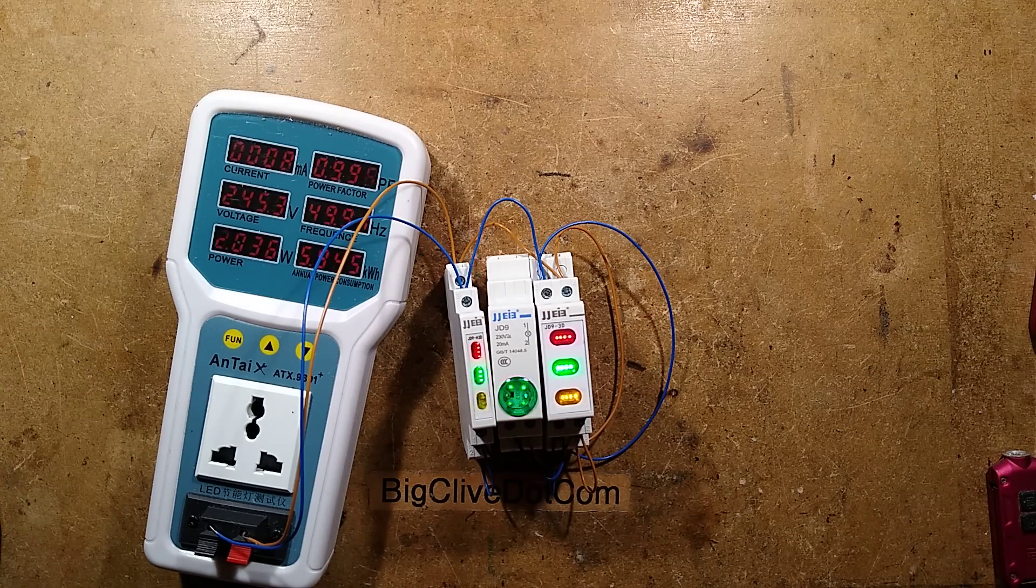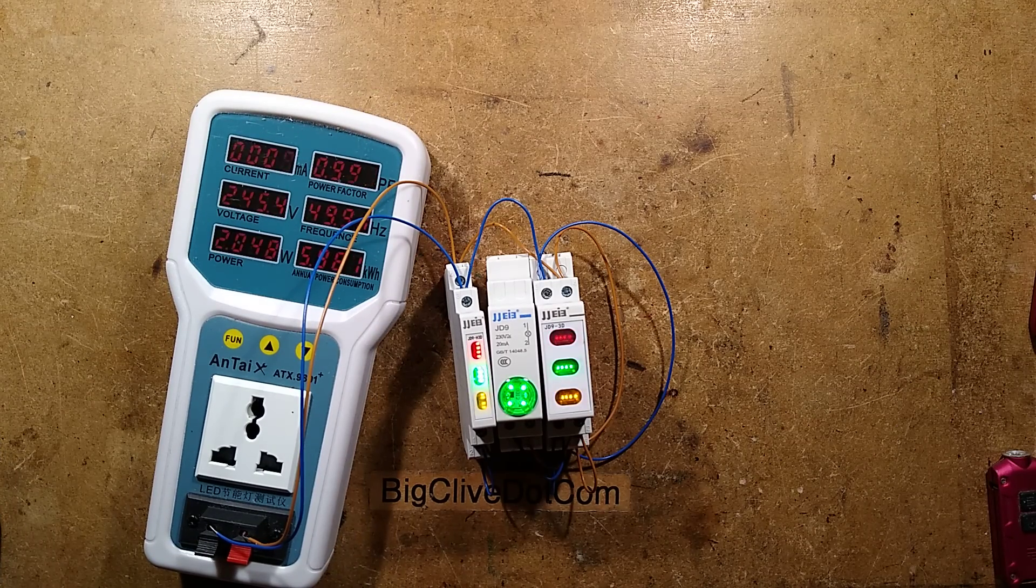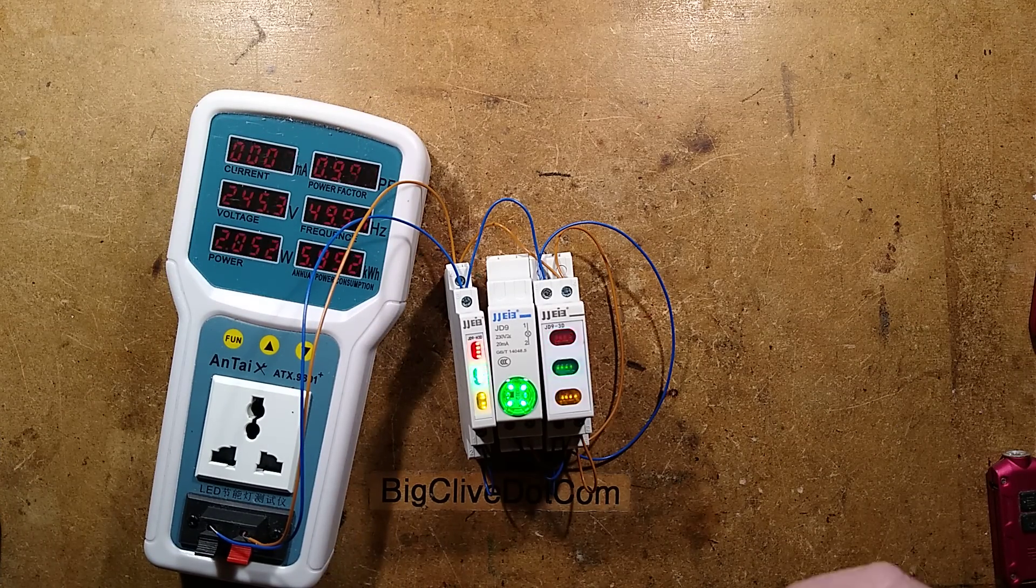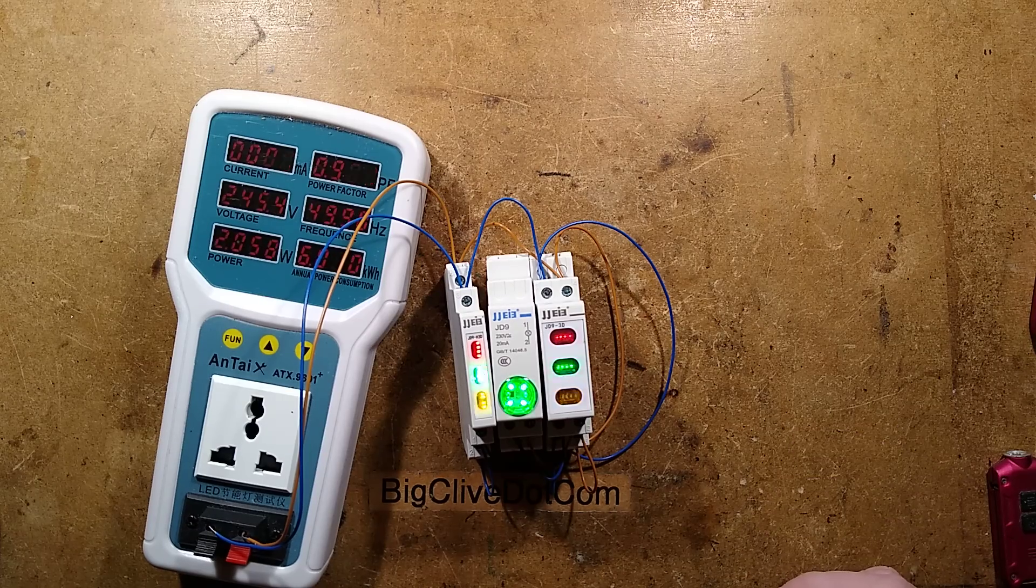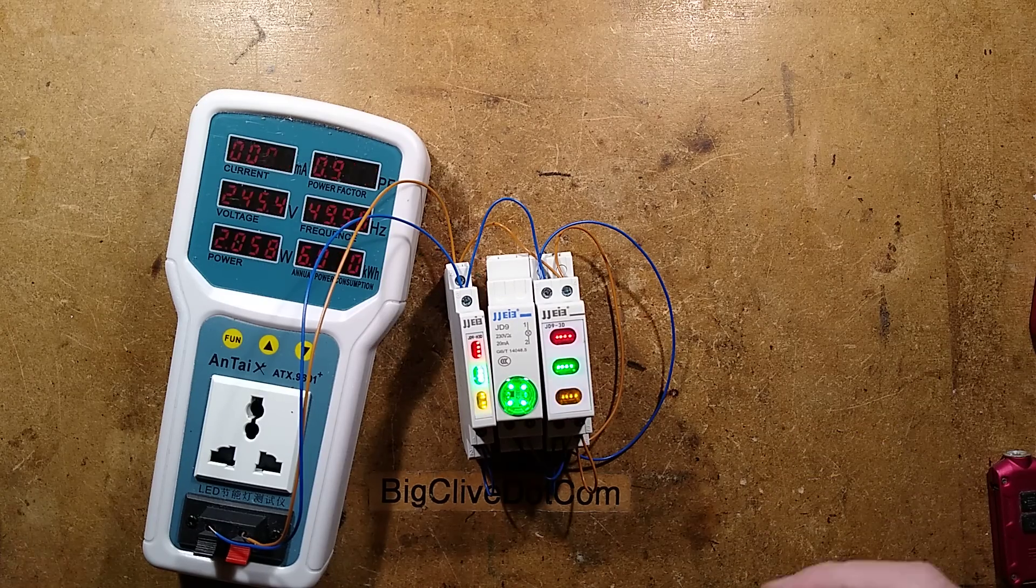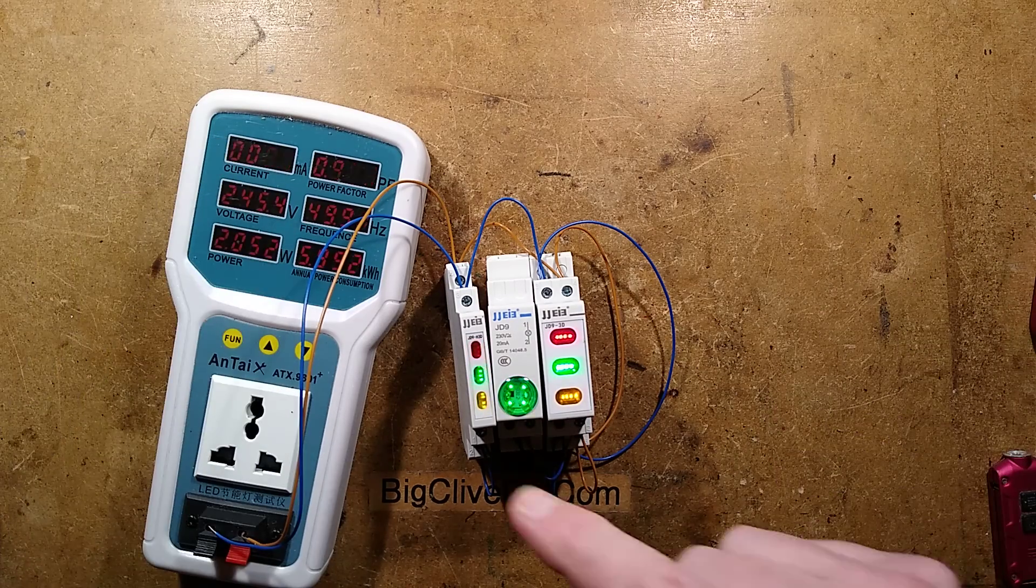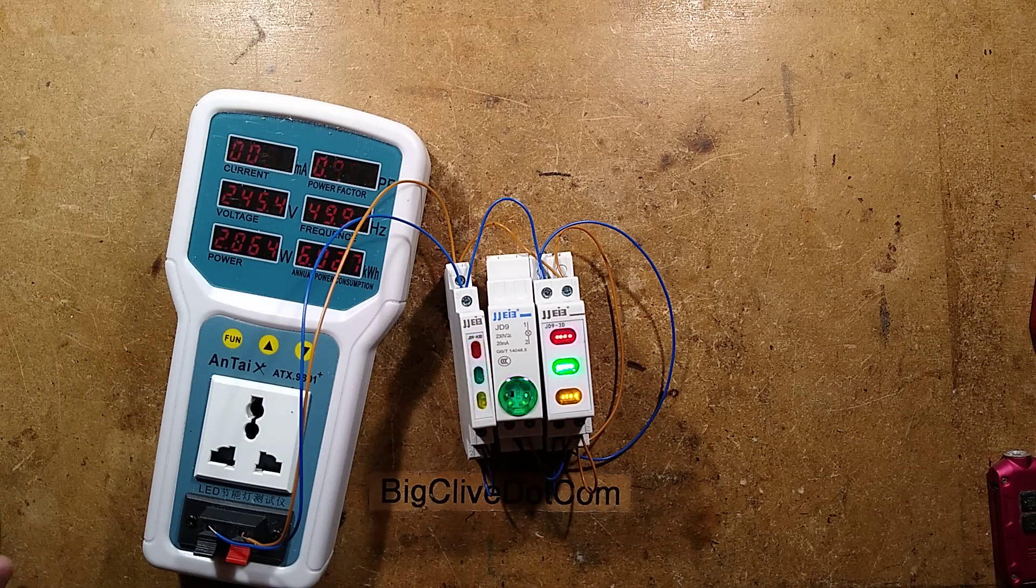What's it showing? It's showing two watts, 0.998 power factor, that means it's resistive. Eight milliamps. So roughly one milliamp each, there's seven of them. That bit of it is done. Let's open them up.